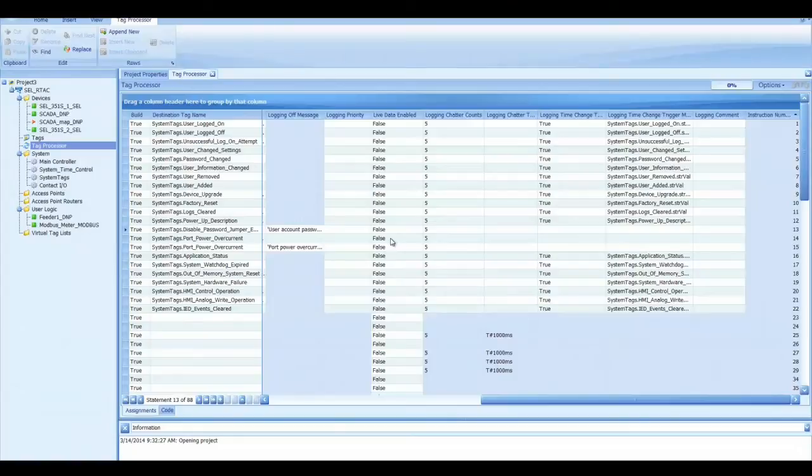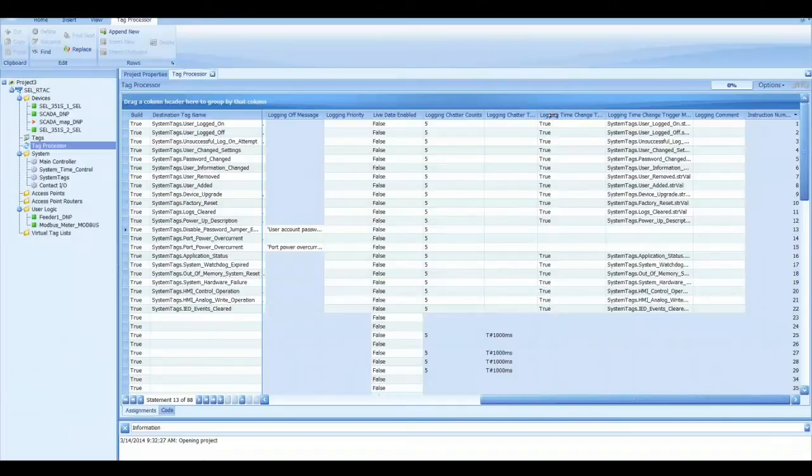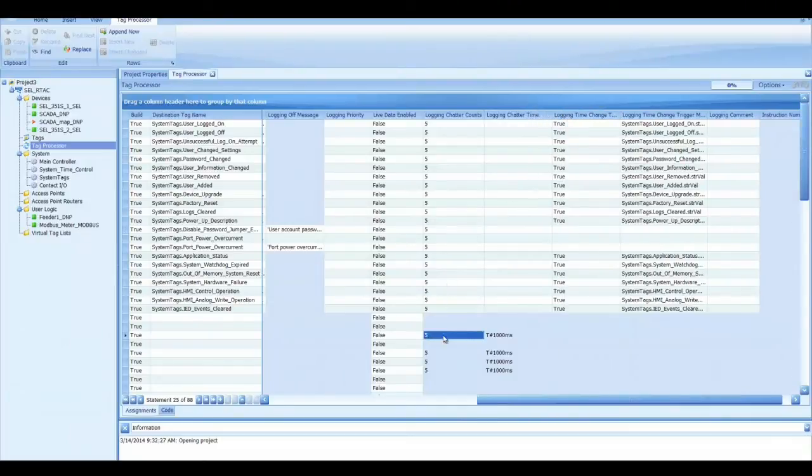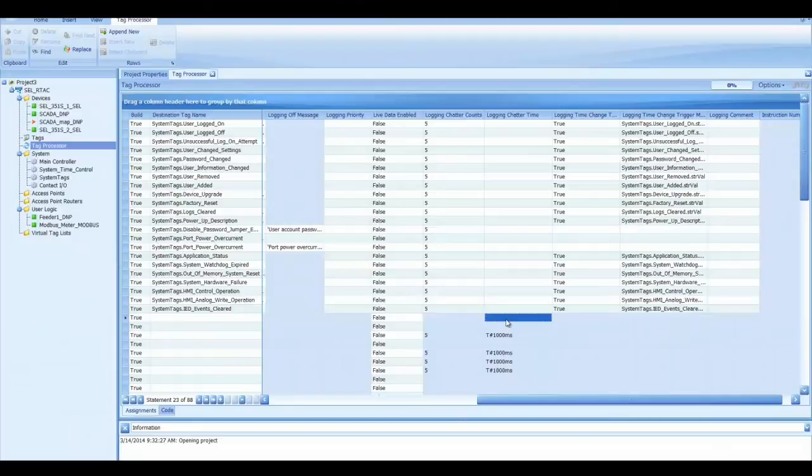And you don't have to do any other work. It just shows up. The logging chatter counts and time, like in this example there's a 5 and a 1,000, so that means if it changes more than 5 times in 1,000 milliseconds or 1 second, then it will be considered a chatter and it won't log all of the chatter items.